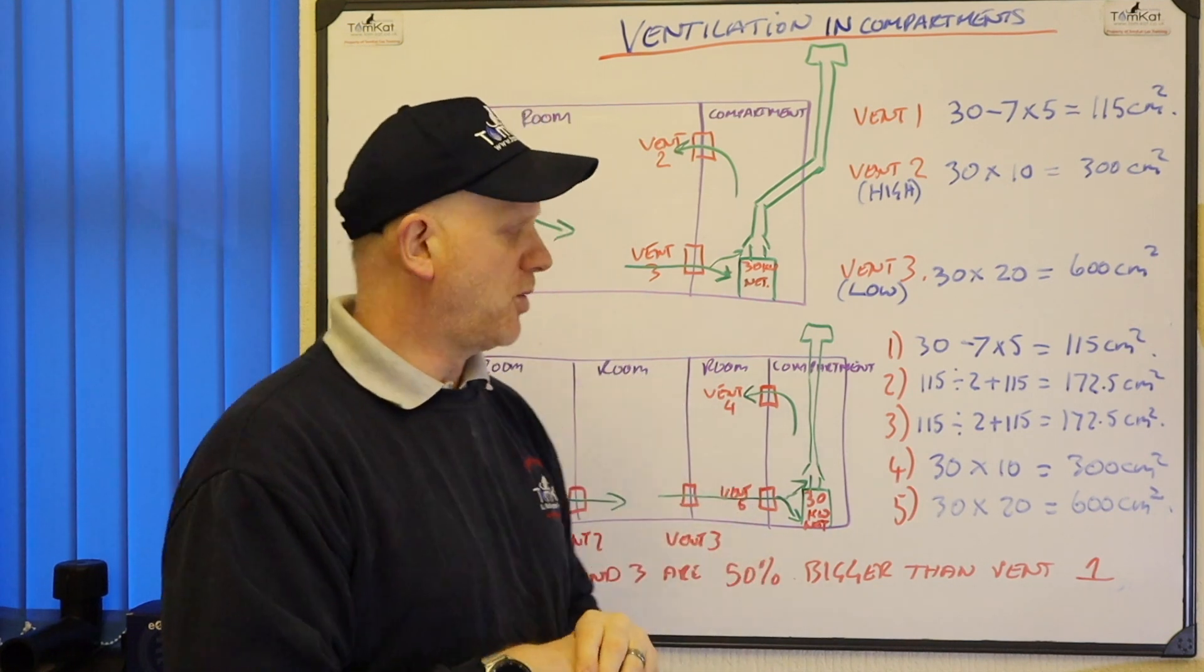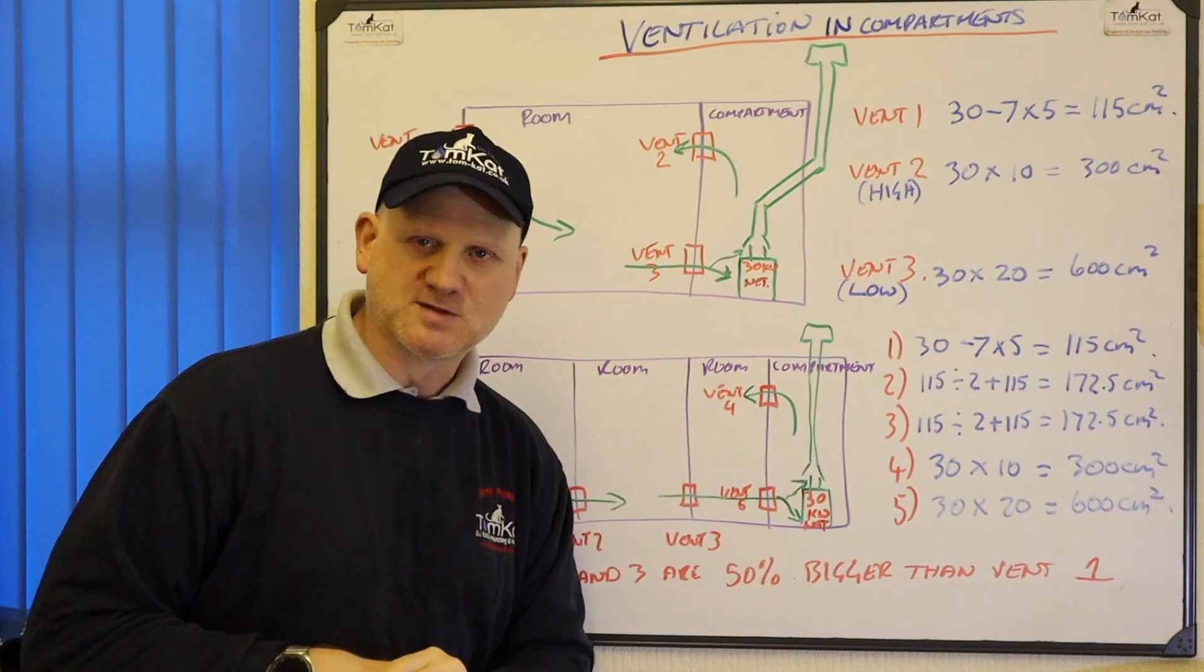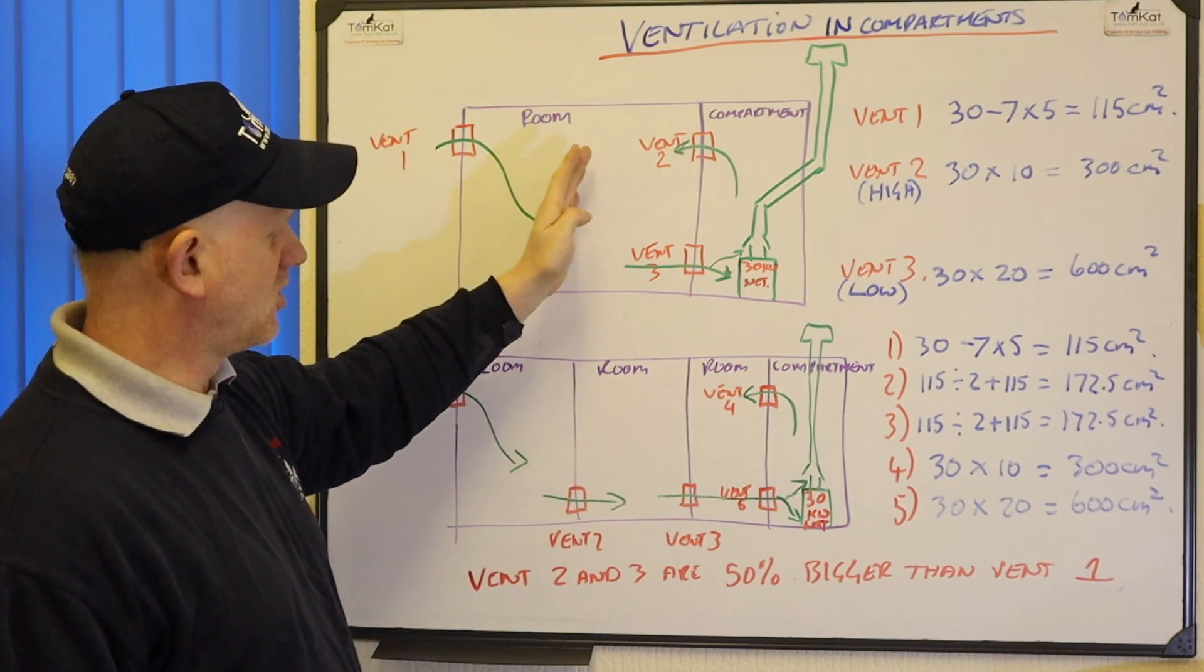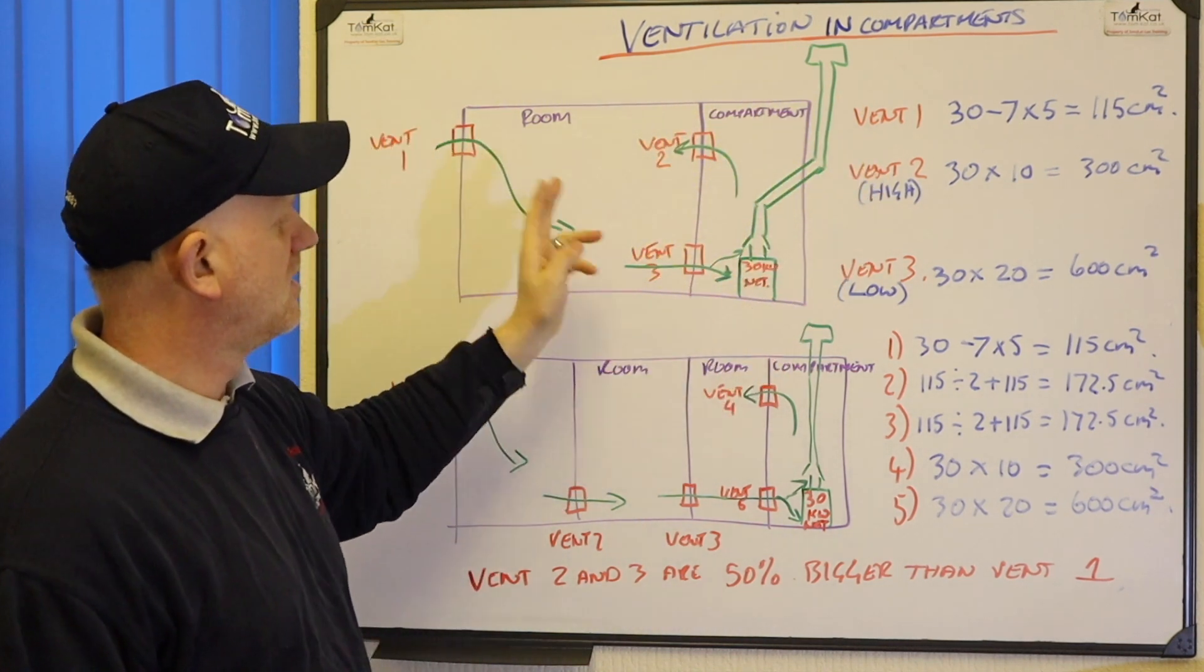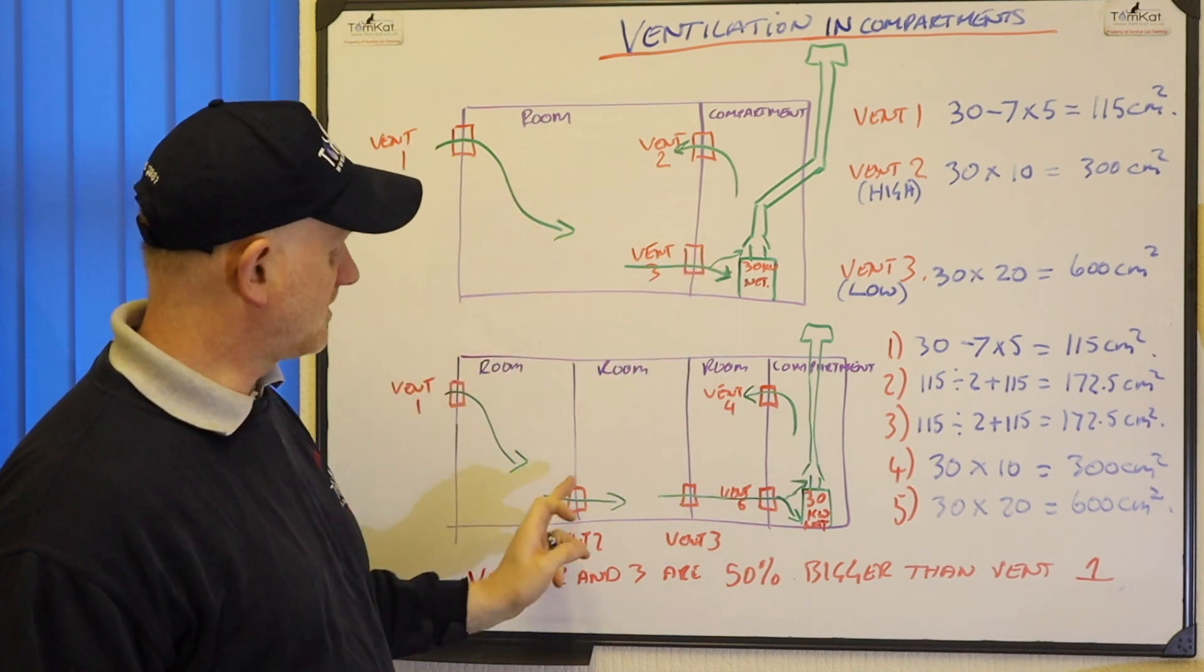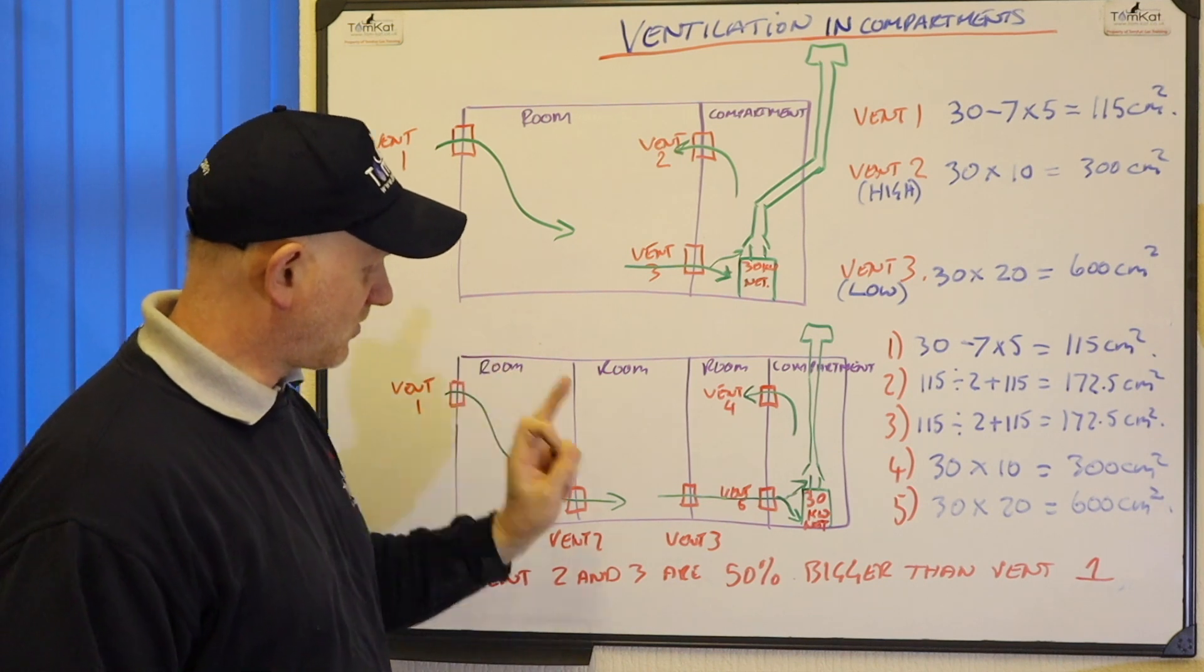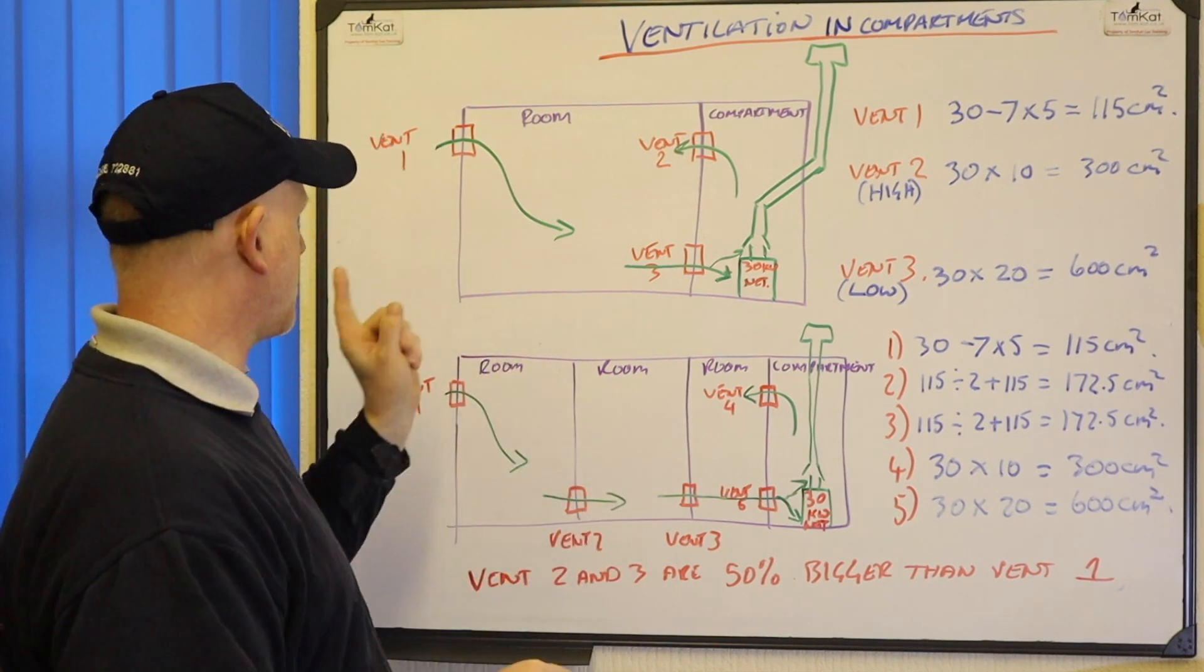Let's up a notch and look at it passing through two or more rooms. So if it passed just through one room like we did before it would be this one. If we pass through two rooms and then into the compartment we just need the vents to be the same. So passing through, but because we're going through two or more rooms, vents 2 and 3 need to be increased by 50% from the outside vent.